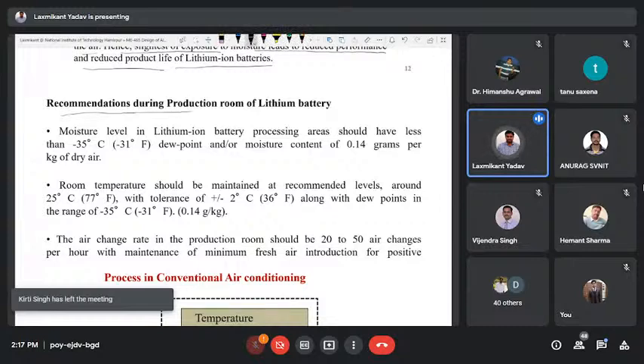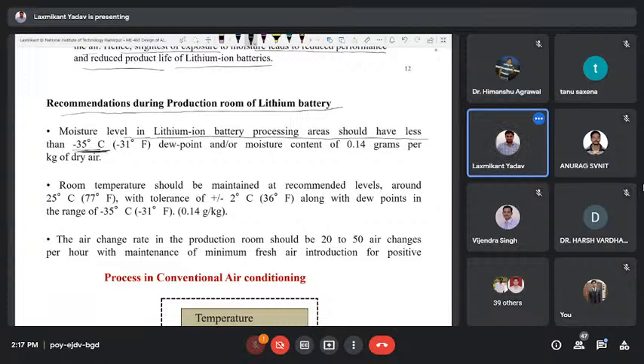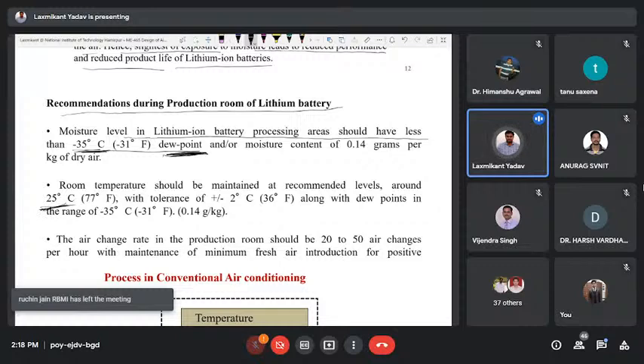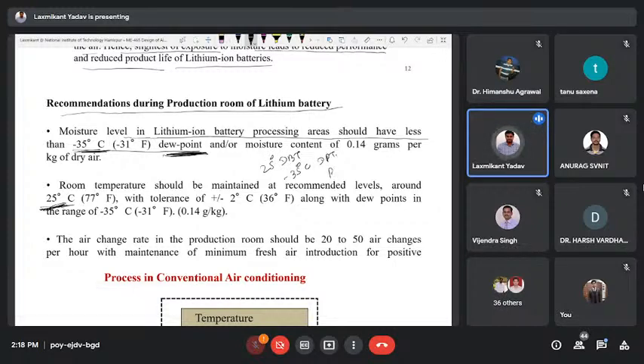So what are the recommendations during the production of lithium battery? The moisture level in the lithium battery processing area should be less than minus 35 degrees Celsius, and this is the dew point, not the dry bulb temperature. Minus 35 degrees Celsius dew point temperature, and room DBT is 25 degrees Celsius. If we calculate for 25 degrees Celsius DBT and minus 35 degrees Celsius DPT, your relative humidity will be around 0.7%. So this much relative humidity is required for the production room of lithium ion battery, and this much relative humidity we can easily achieve by the desiccant wheel system.